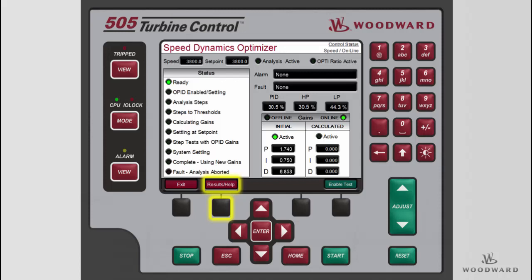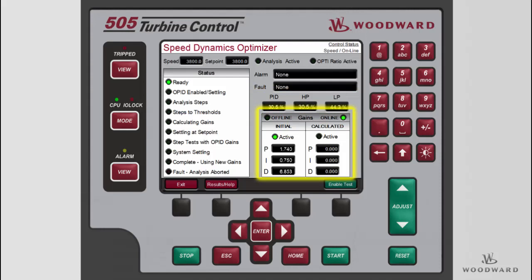Most of the time, an alarm or fault indicates a problem with the steam turbine system that is outside of the PID tuning. The PID Optimizer test can provide system diagnostics through the alarms and faults. Details for each alarm and fault, as well as a possible root cause, can be found in the product manual. Below the alarms and faults, the current values for the speed PID output and valve positions are given. The Gains table in the bottom right of the screen provides information on the initial system gains as well as the calculated gains from the optimizer test. The offline and online LEDs indicate which set of gains will be calculated, and the active LEDs indicate which gains are currently active. Prior to a test being enabled, the initial gains will be active.